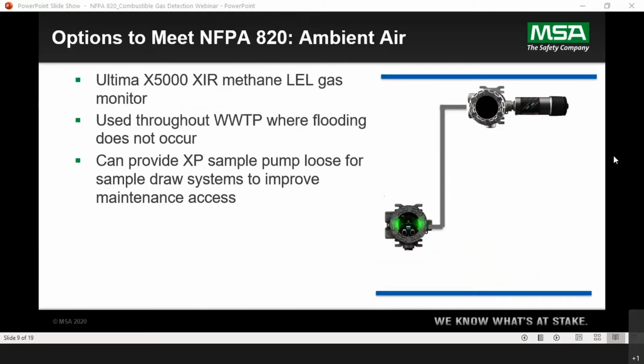So, ambient air. Here's the first one I'm mentioning, and this is our traditional diffusion design for monitoring air. You see the Ultima XIR, X5000 Plus is going to be mounted on the ceiling. And the transmitter is down here below, at eye level, and there's a sensor. The concern is putting these detectors in.